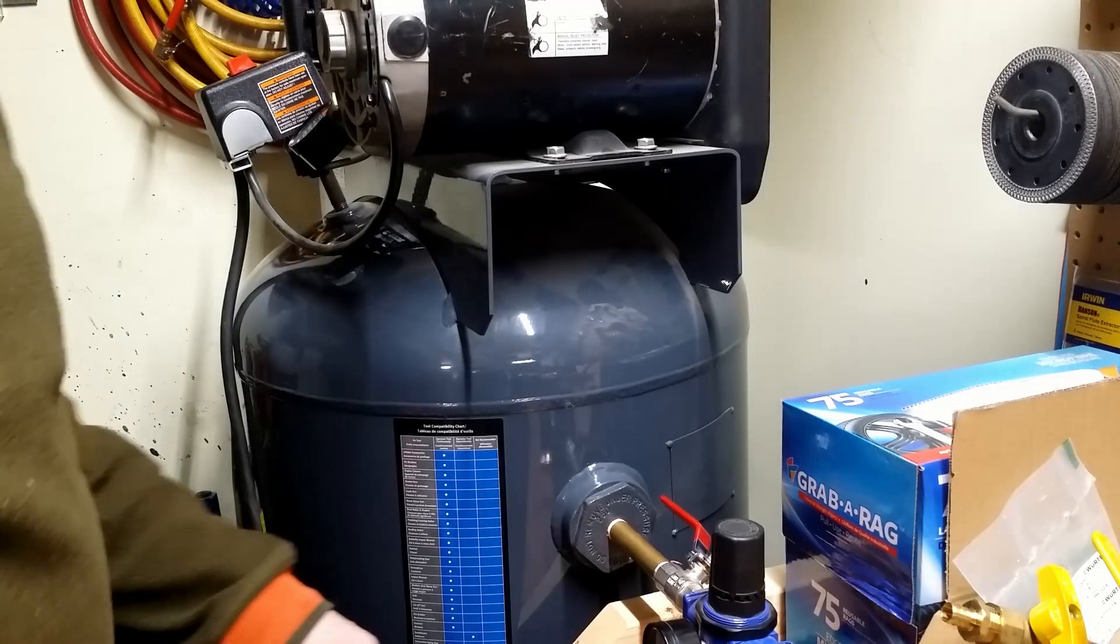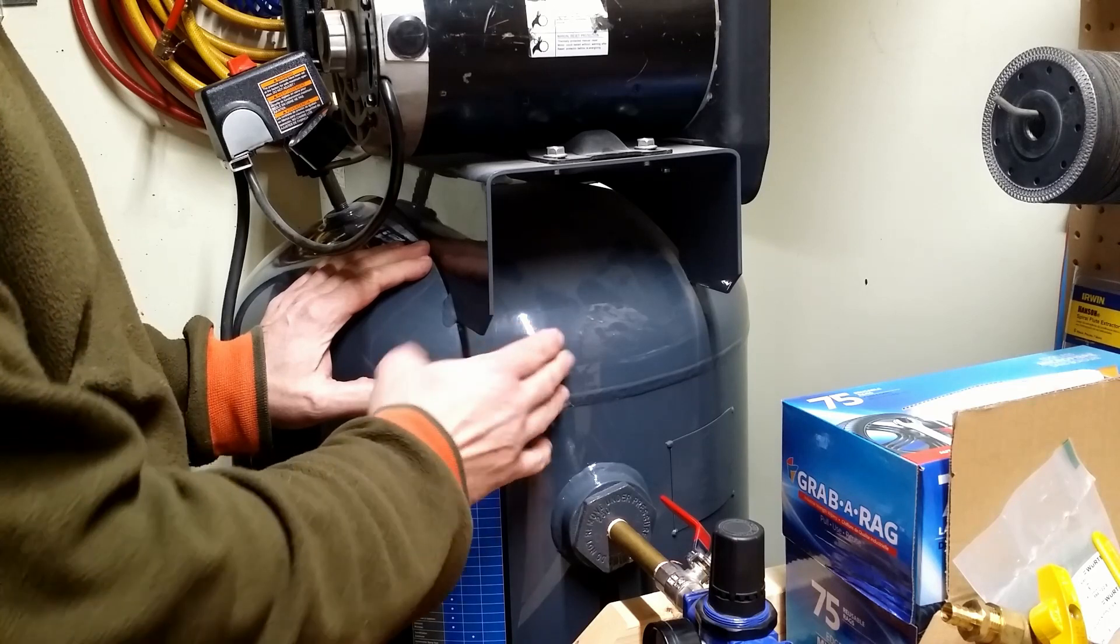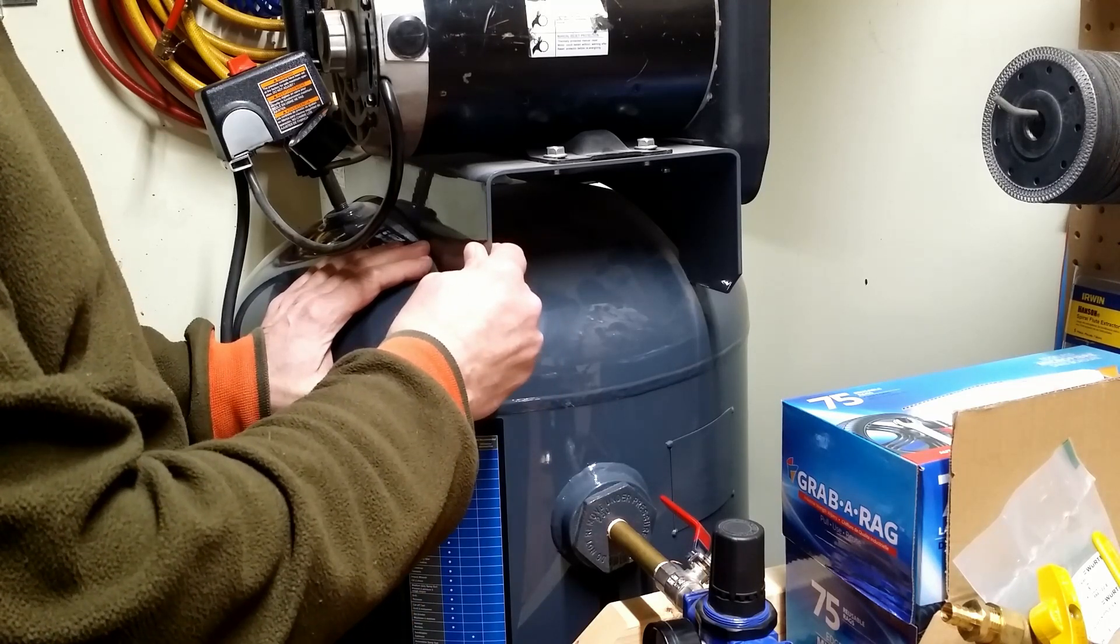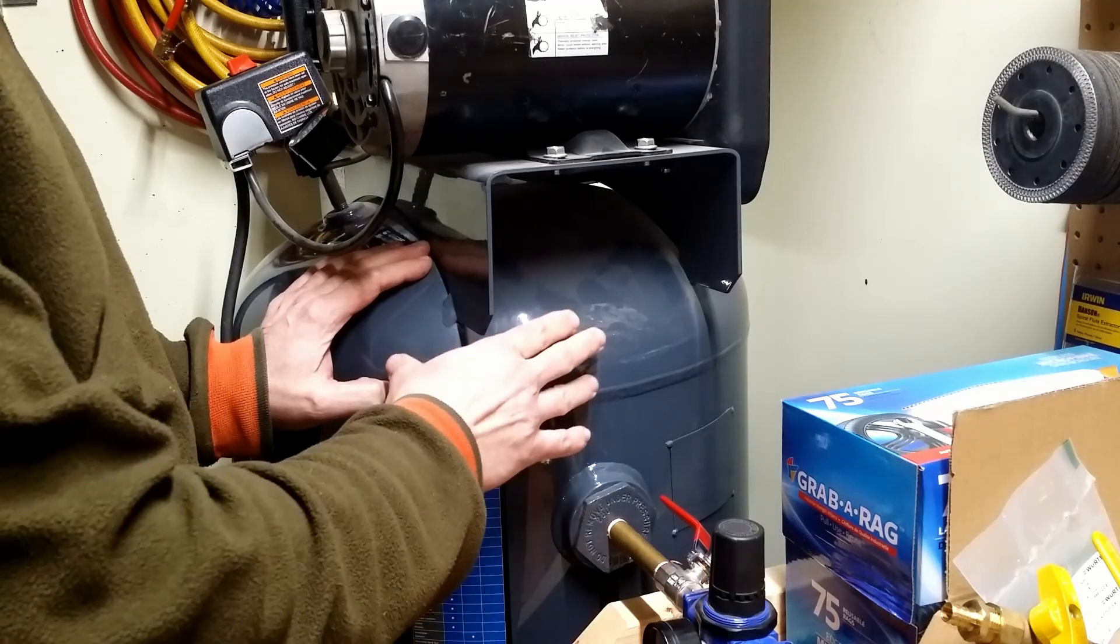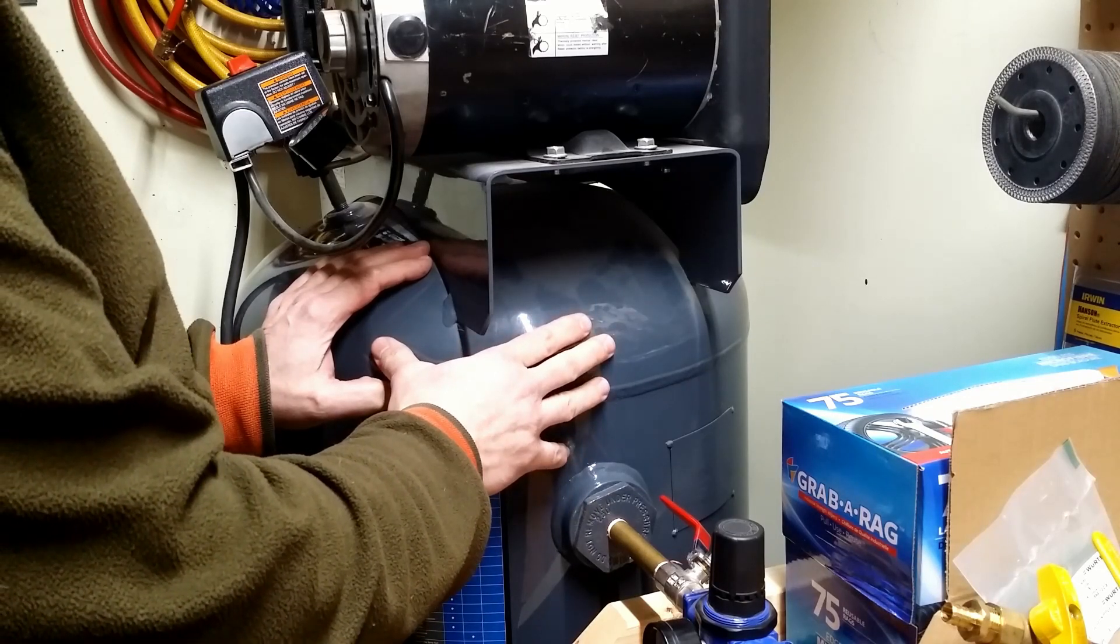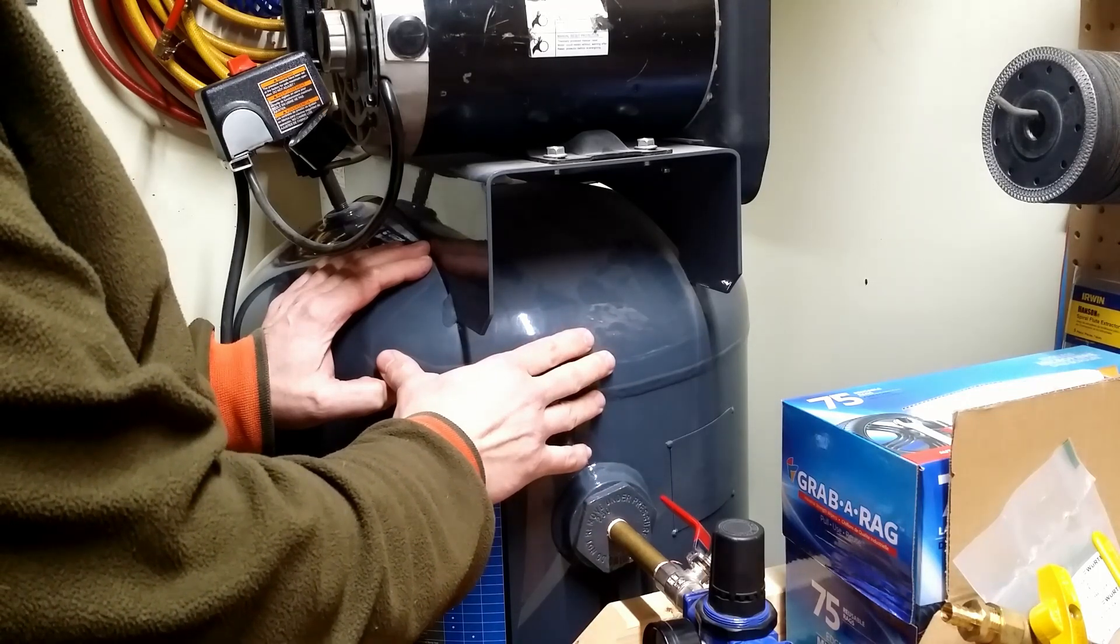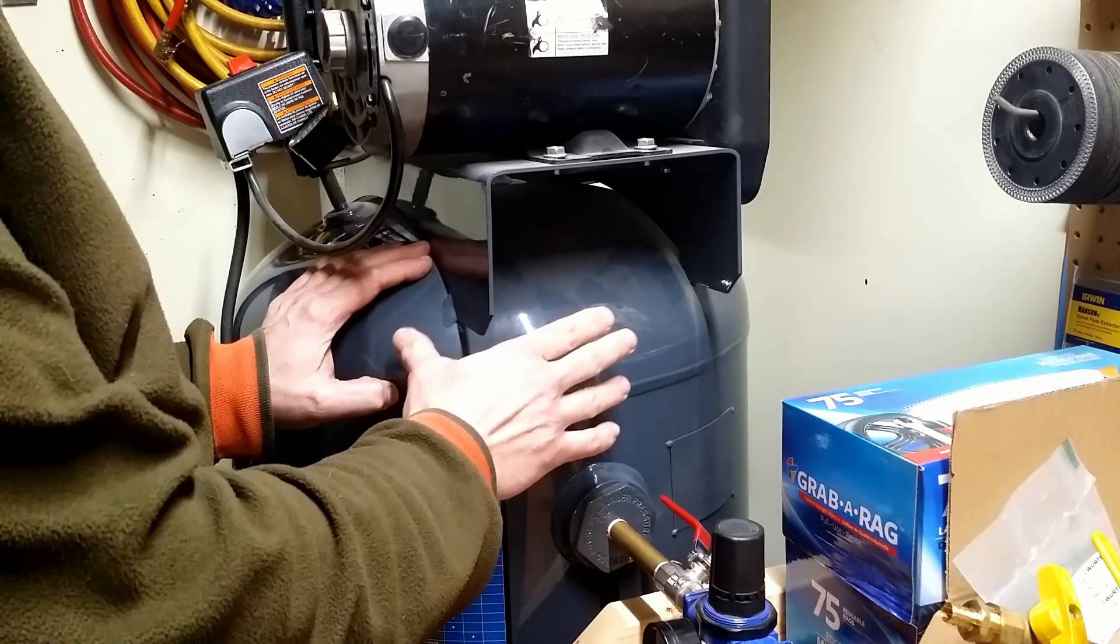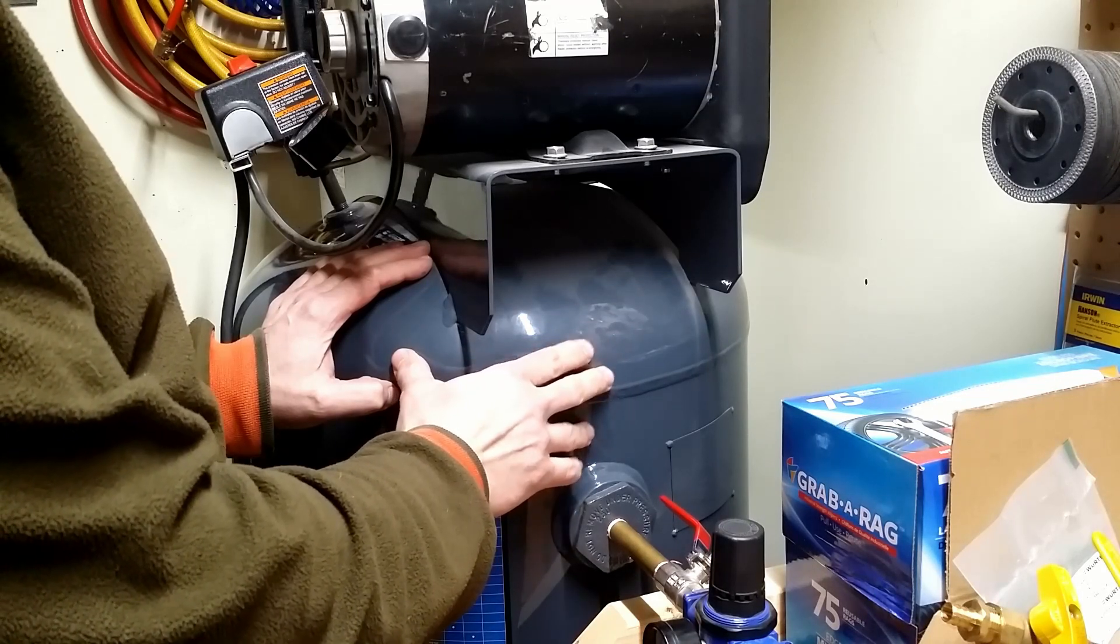I will start my project with hydro testing the tank. I will fill it with water, close all ports and apply pressure from a pressure washer. The testing will be done at 150% of the working pressure of this tank. It is specified to be 150 PSI so I will test it at 225 PSI. Why do I test it with water?